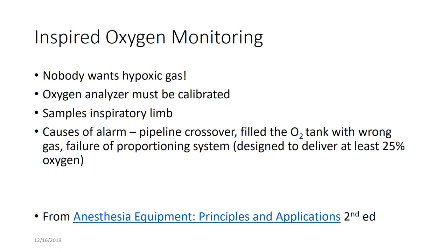Inspired oxygen monitoring — we don't want to give a hypoxic gas mixture. The oxygen analyzer must be calibrated to room air. It samples the inspiratory limb, and reasons you may get a low oxygen alarm include a pipeline crossover, an oxygen tank filled with the wrong gas, or the proportioning system failing.